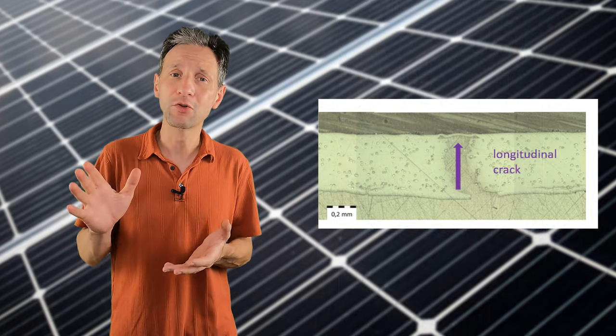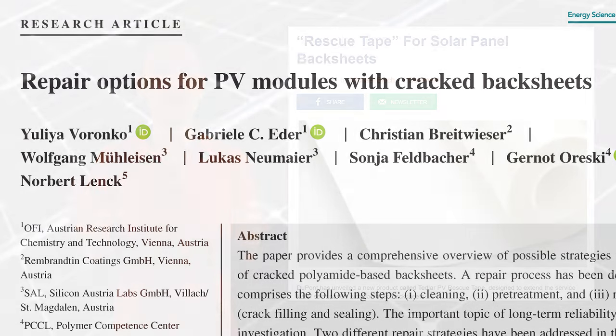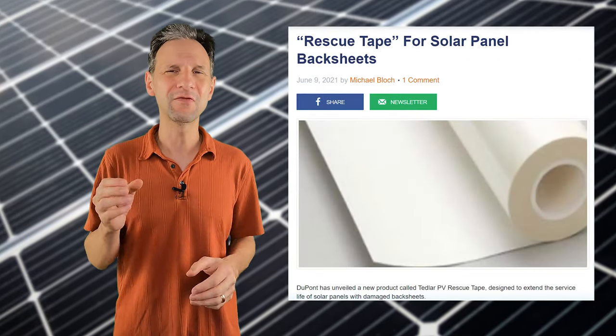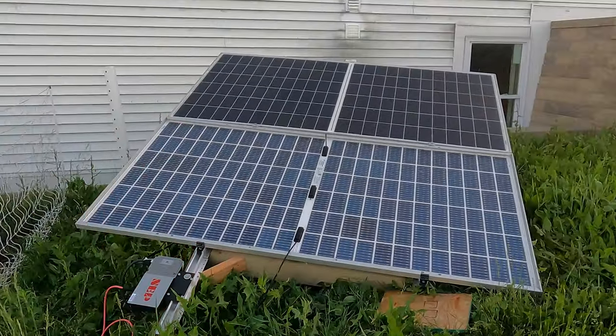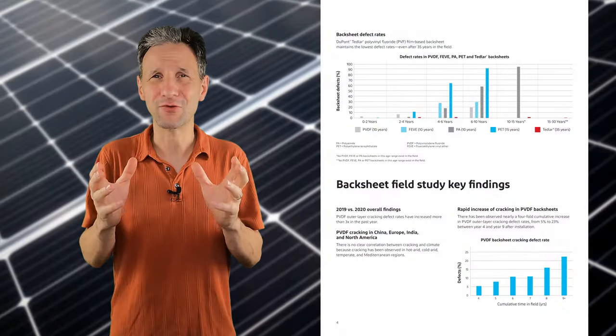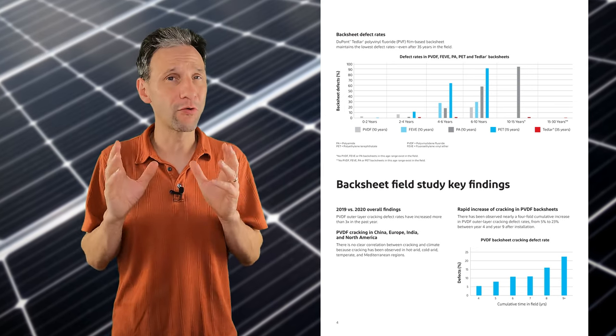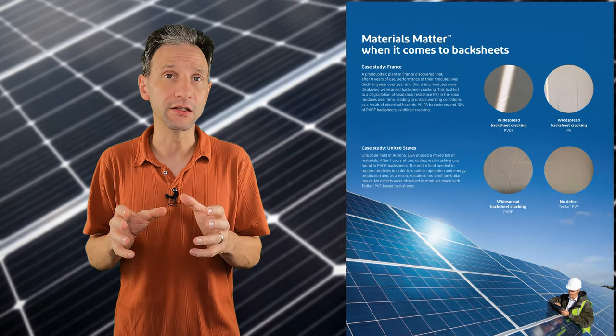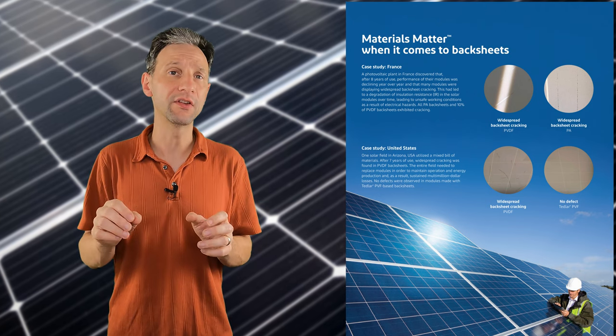If the module is not yet compromised, it's possible to repair the panels to prevent further degradation. I've left a link in the description to a couple of solutions for repair. The two most common methods are a sticker, which doesn't seem very robust to me, and a rolled or brushed-on sealant that seals the cracks, although repair longevity is not well known. One easy way to reduce the risk of a backsheet failure is to buy bifacial panels, since they have a glass back — there's nothing to break down. This is a really great improvement in solar panel longevity. You can also buy quality modules from a reputable supplier and check the bill of materials for the actual backsheet. DuPont has published a paper analyzing materials used in the market and lists which ones have the best performance.